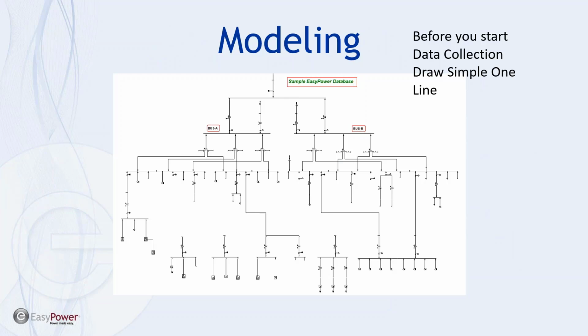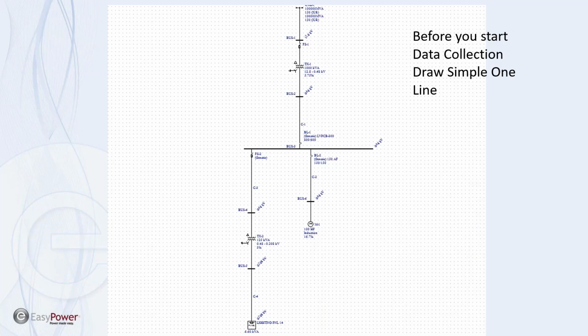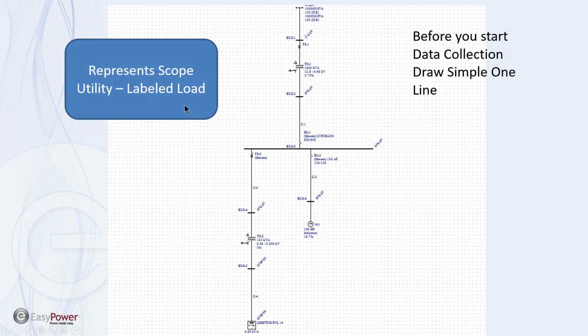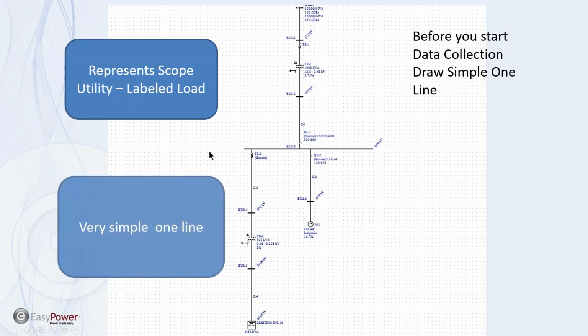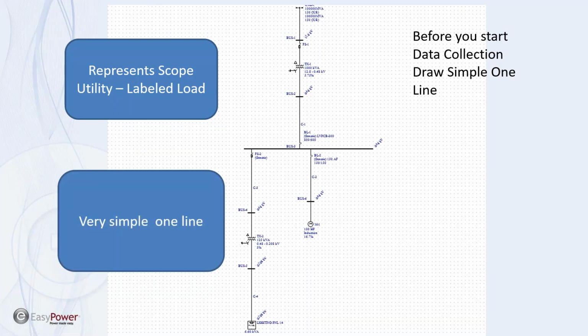Before you start data collection, I suggest you should draw a simple one-line diagram, not too dissimilar from what I just did with the electrician from Oklahoma, but make sure that you, or whoever's going to be doing the data collection, understand the parameters that affect the incident energy calculations. And so I suggest you start with a very simplified connection between the utility through typical examples of the loads, transformers, switchgear, and ultimately out to whatever a typical panel or motor is that you're going to serve as a load, and make sure you can get the result that you're expecting to see. Because if you don't have the correct information in that one-line, then you're not going to get the results, and consequently you're going to have to make multiple trips to the site, which causes the cost of the study and the time spent on it to go up exponentially.